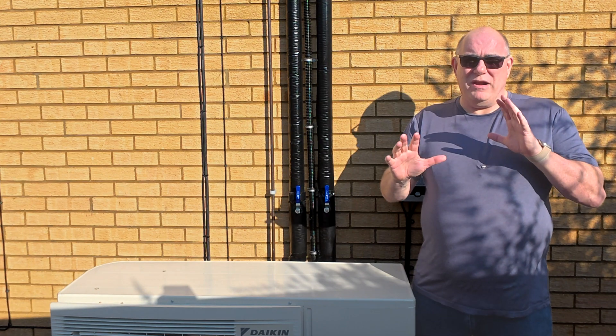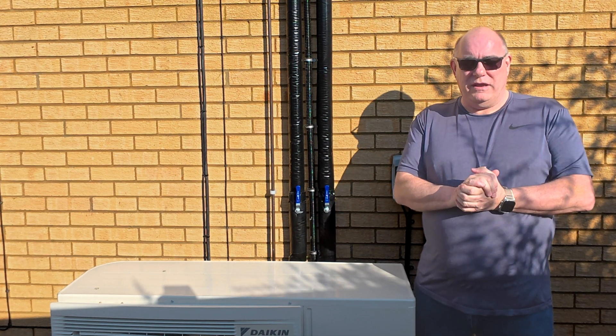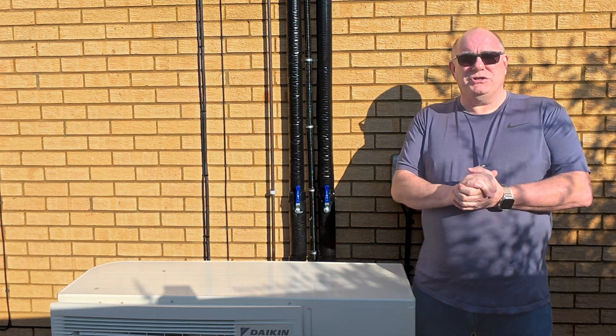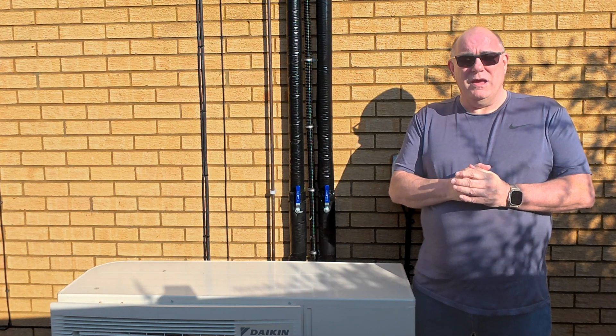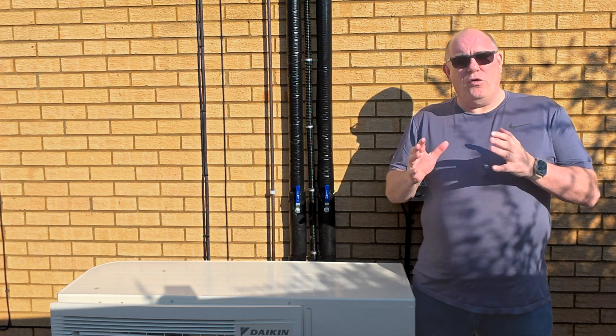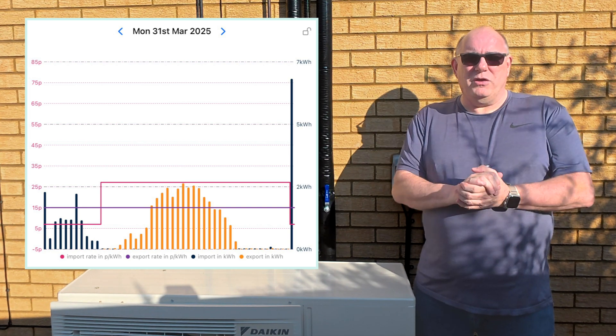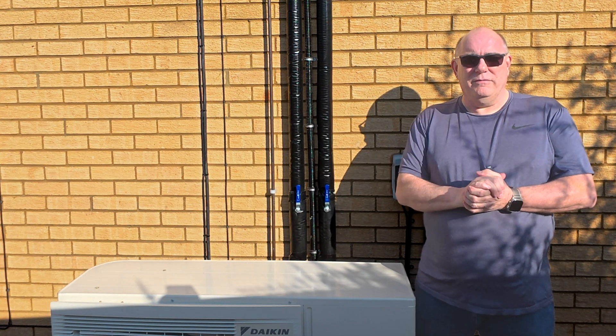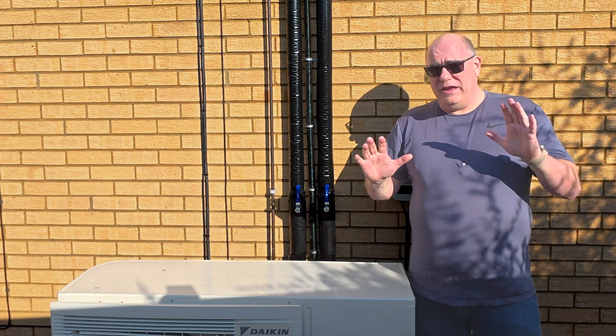We have made a few changes — the system is not running exactly like it was a year ago. As the clocks have now gone forward at the end of March, we've made a couple of changes because the weather has got so much better. We've actually reduced the temperature in the house by about one or two degrees depending on the time of day, which means the heat pump isn't working as hard as it was back in February and early March. We've also stopped force exporting from the battery. On these beautiful days we've been exporting nearly 40 kilowatt hours, so we don't really need that little bit extra from exporting another 10 or 15 kilowatts from the batteries. It's less cycles on the batteries and better for them over their life.